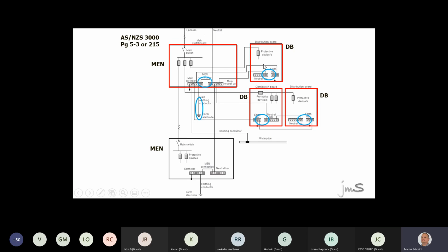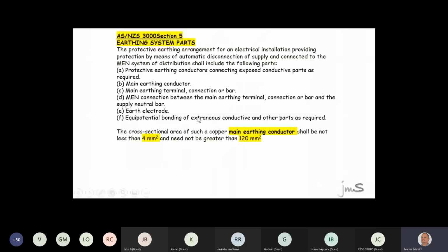Next week when we do testing, I'm going to show you why there's no link between neutral and earth. Also, the earth here is not allowed to carry operational current, but if you put a link in, there will be operational current. Now, the MEN system, that peg on the ground, do you all agree that peg must be connected to the earth bar? With what type of conductor? You all agree, a main earth conductor. The main earth conductor can be anything between 4 mil and 120 mil. You base it on the main active coming in.